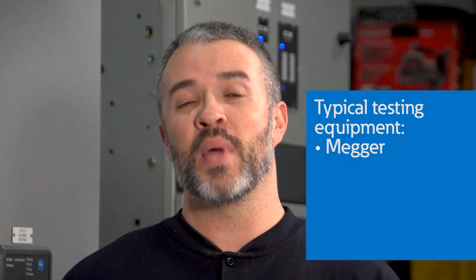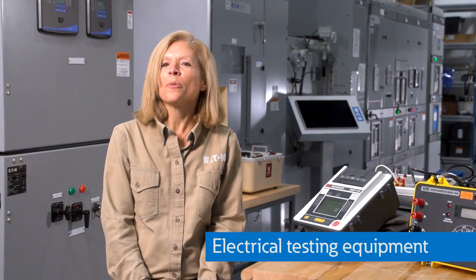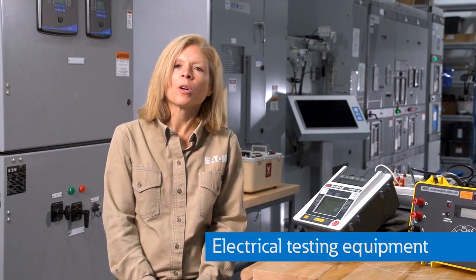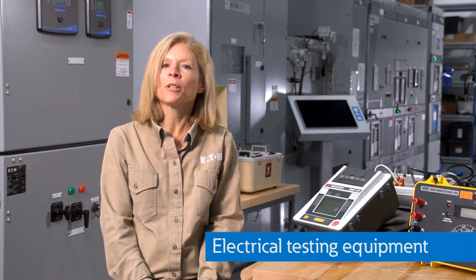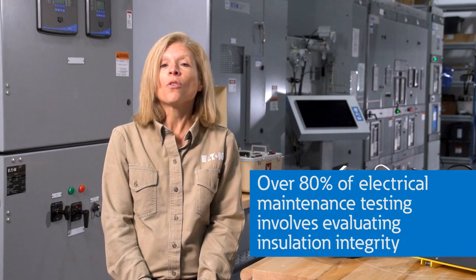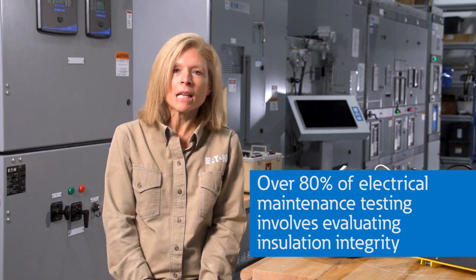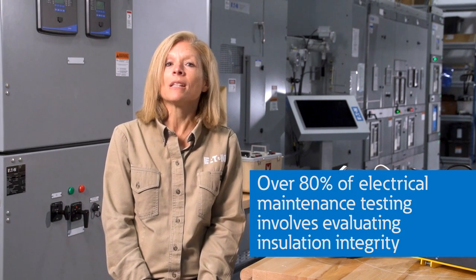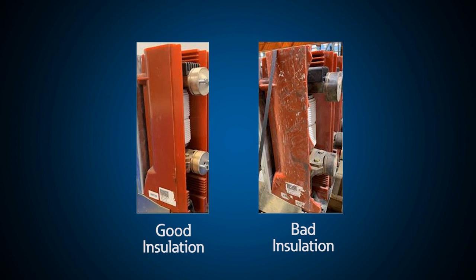In the next section, we will discuss some of the most common types of test equipment and procedures used for electrical testing and maintenance, including Megger, high pot, ductor, high current injection, and thermal imaging. Electrical equipment requires good insulation to work properly and ensure the safety of personnel and equipment. Over 80% of electrical maintenance testing involves evaluating insulation integrity. A good insulator will have a high resistance, and a bad insulator will have low resistance.